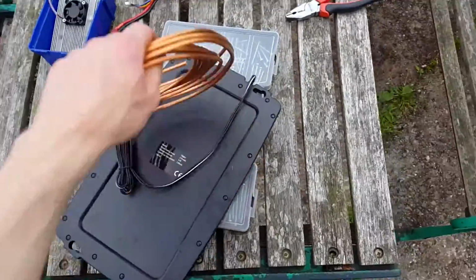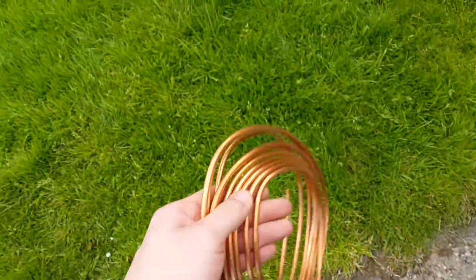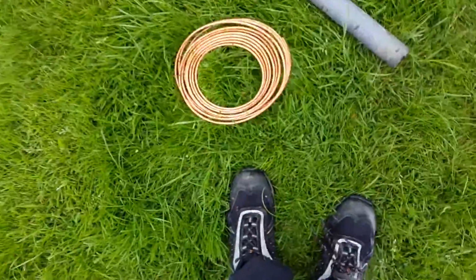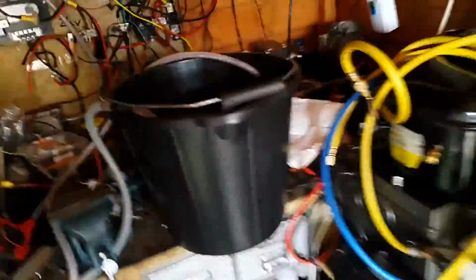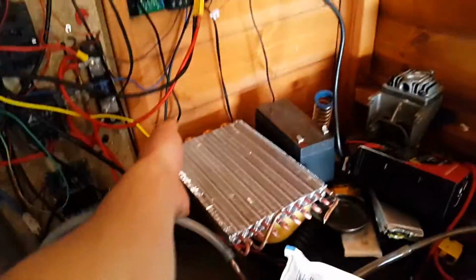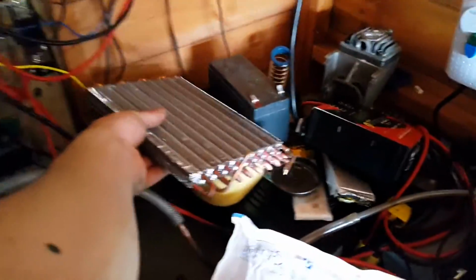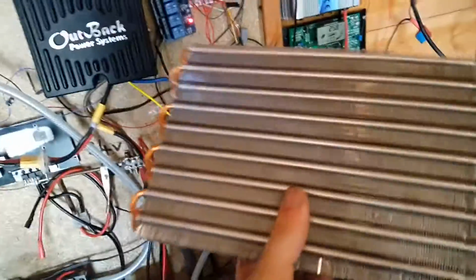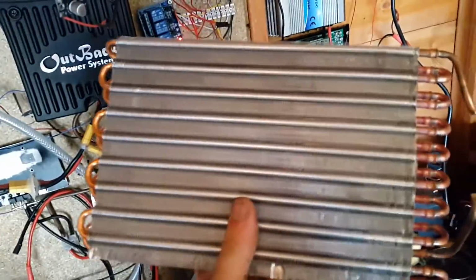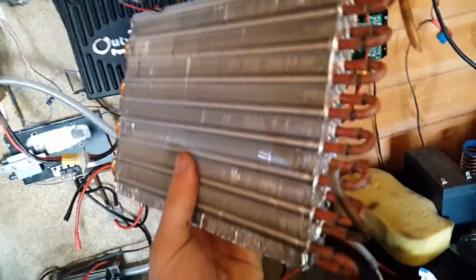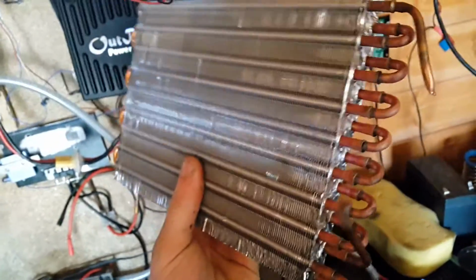I'm onto the stage of winding the new condenser. Here is where I'm up to. The condenser has now been removed. It is very fragile, the fins are very thin. And all I've done is I've just crimped the ends shut to keep out contaminants and moisture.